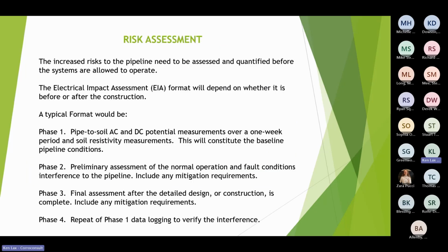That risk has to be assessed. Now, there's a fairly routine way that we tend to deal with assessing the risk. It depends a little bit on what phase you're assessing the risk. If it's at the planning approval stage, we have to do a preliminary assessment, which I'll come to a bit later. But a typical format would be to go to the existing pipeline and measure the AC and DC potentials over a 1 week period. That's to give a spread of loads and utilization.